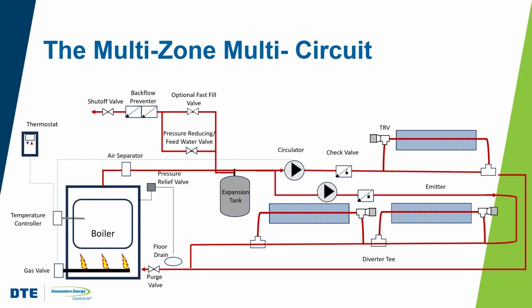Additionally, if you've got a single large pump and only one zone, for example, is calling for heating, you may have a little too much flow, or a little too much noise in the system. So those are just detractors from homeowner comfort. But the nice thing about this is that each zone gets really close to the same incoming temperatures. So that generally means that the emitters can be smaller, and the temperatures of the water in the distribution system may actually be lower, and this may improve overall system efficiencies.